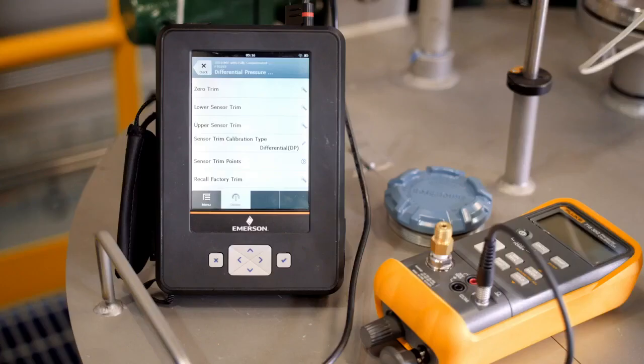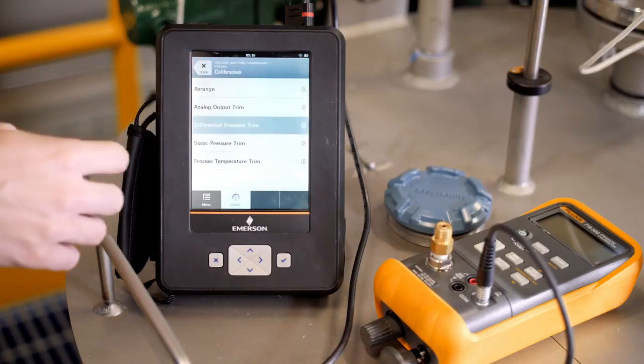The next step in calibrating a multivariable transmitter is to calibrate the static pressure sensor. The static pressure calibration follows a similar procedure as the DP sensor. The static pressure trims can also be accessed through the calibration page by selecting static pressure trim.